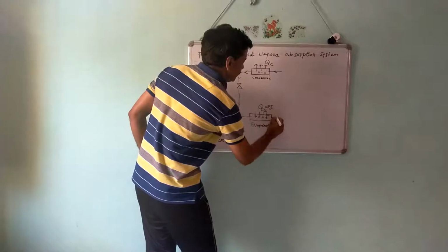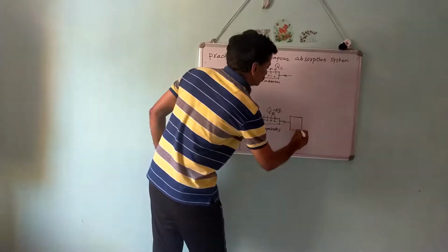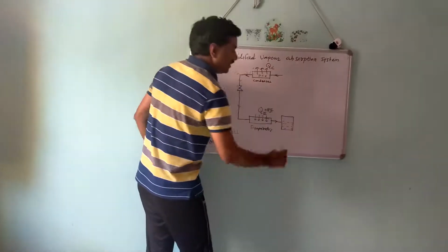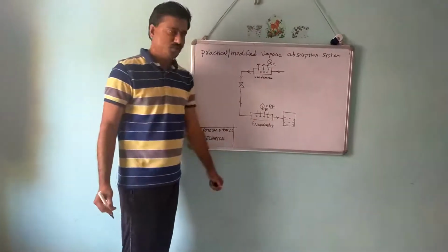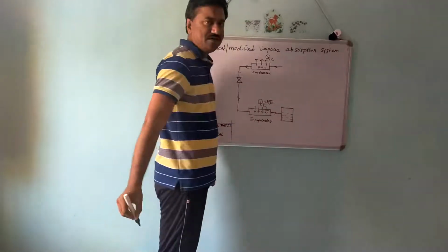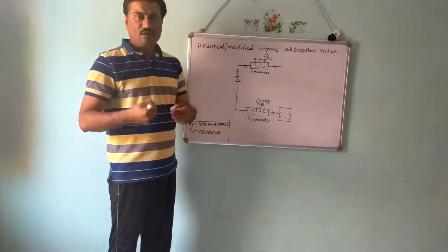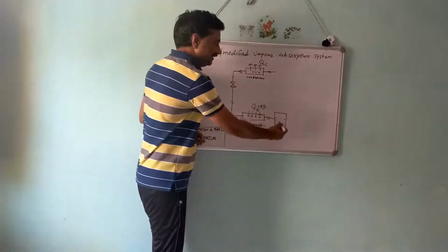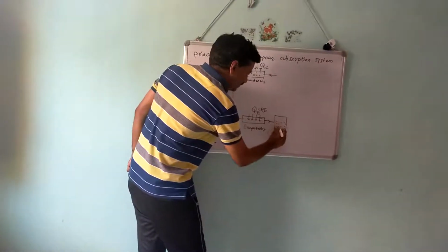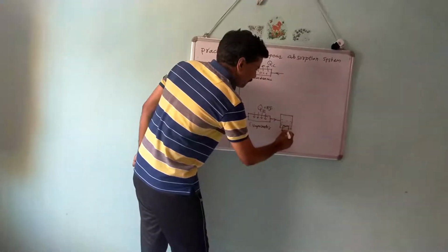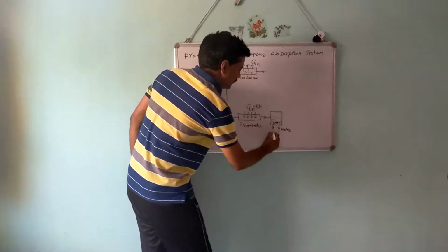And then these ammonia vapors are absorbed in an absorber. The absorber contains an absorbent, which is water, and water has a strong affinity for ammonia. So ammonia vapors are totally absorbed by water, and due to absorption of ammonia in water, the temperature of this solution will increase. So to keep the temperature constant, water is continuously circulated in the absorber. This is the absorber, the total assembly.